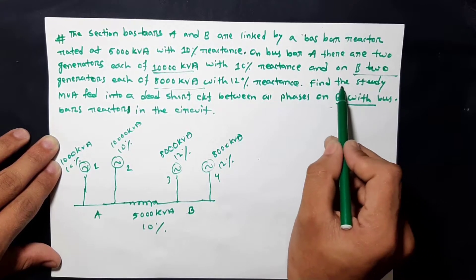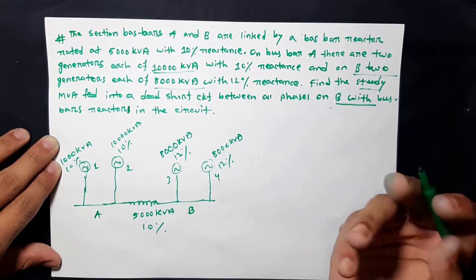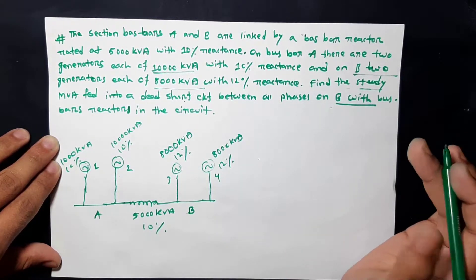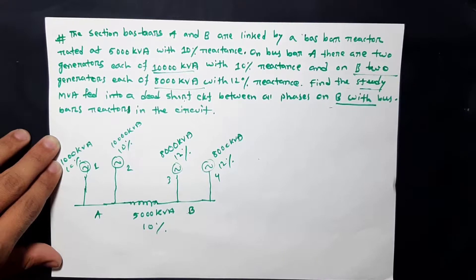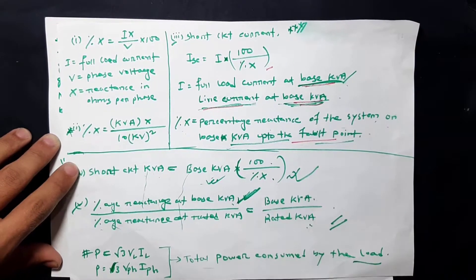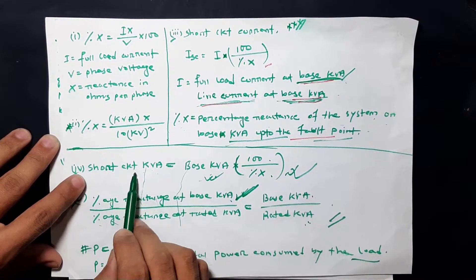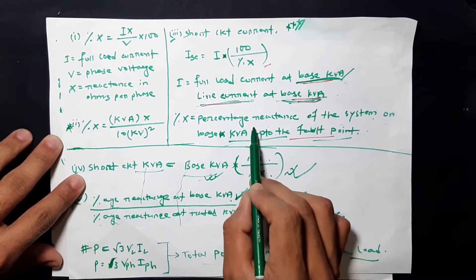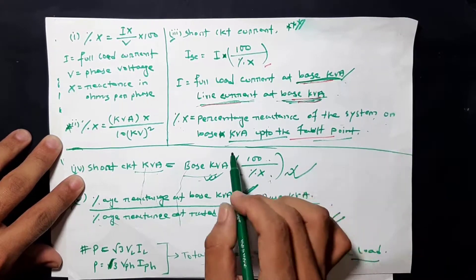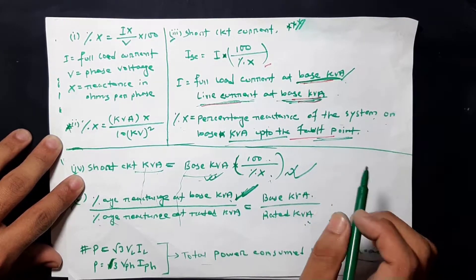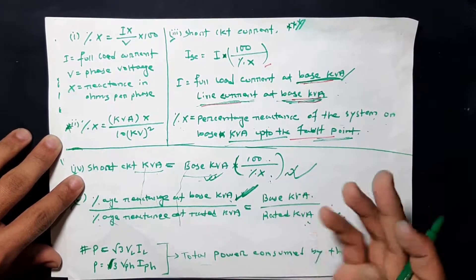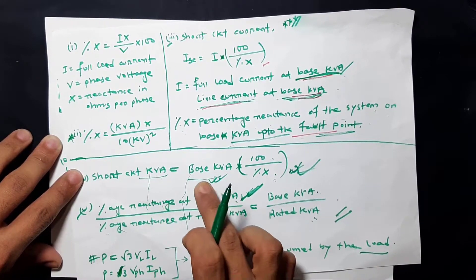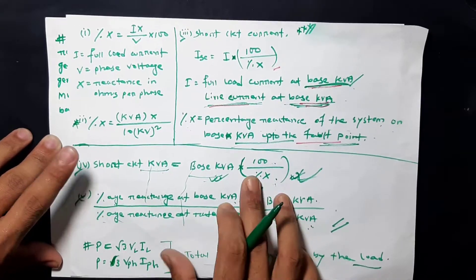We have to find the steady-state short circuit MVA. The short circuit MVA formula is: short circuit KVA equals base KVA multiplied by 100 divided by percentage reactance (%X). Similarly, short circuit MVA equals base MVA multiplied by 100 divided by percentage reactance.